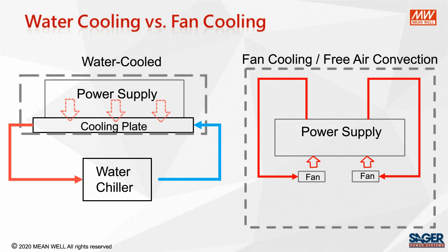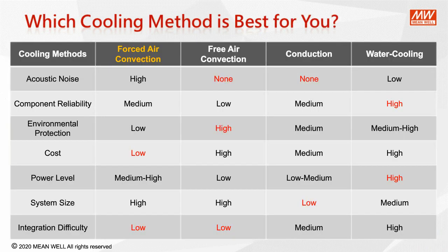So to help determine which type of power supply is the most suitable for your application, we will compare them in 7 different categories. In terms of acoustic noise, free air convection and conduction cooling type wins out since their fan is completely eliminated. For water cooling, there may still be acoustic noise caused by the external chiller.